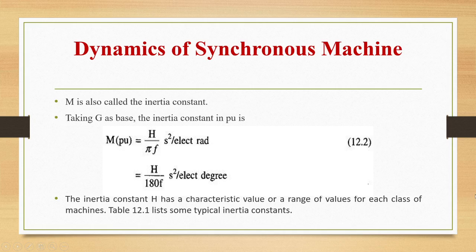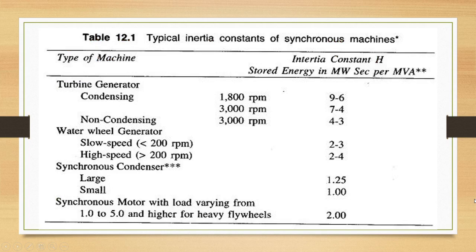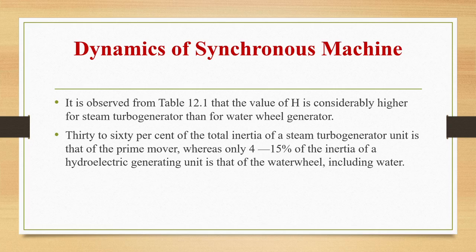The inertia constant H has a characteristic range of values for each class of machine. For turbo-generators (condensing), H = 9–6 for 1800 rpm and 7–4 for 3000 rpm. For non-condensing at 3000 rpm, H = 4–3. Water wheel generators have H = 2–3 (slow speed) and 2–4 (high speed). Synchronous condensers have H = 1.25 (large) and 1 (small). Synchronous motors with varying loads have H around 2. The value of H is much higher for steam turbo-generators than for water wheel generators. About 30–60% of the total inertia of a steam turbo-generator unit is the prime mover, whereas only 4–15% of the inertia of a hydroelectric unit is the water wheel including water.